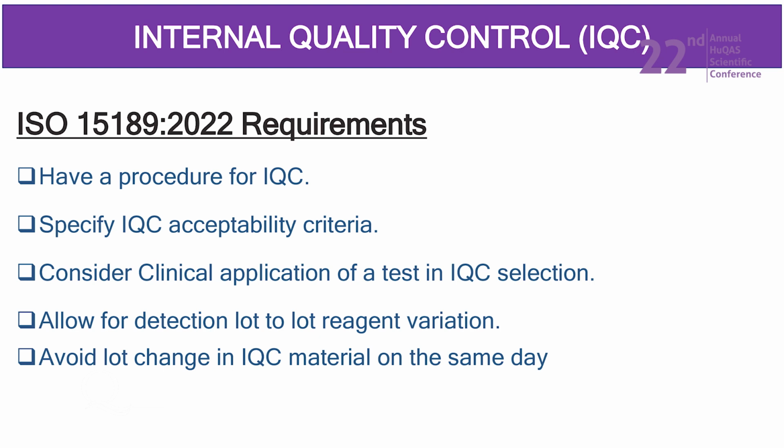And so we are told we must make use of third-party controls because we all have an experience with manufacturers' QCs. Sometimes they may have a bigger range, and therefore no failure is observed in IQC. But when that same machine is subjected to an EQA, you find yourself failing, even if IQC is doing very well.